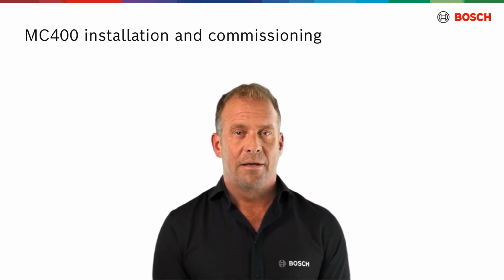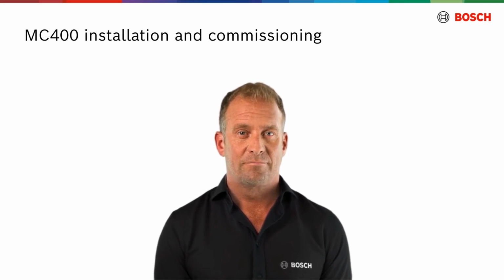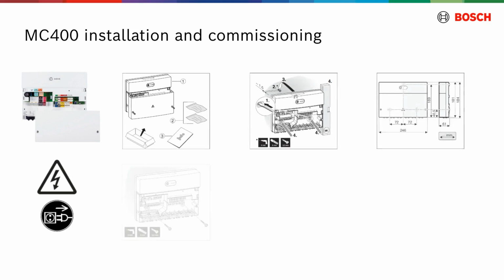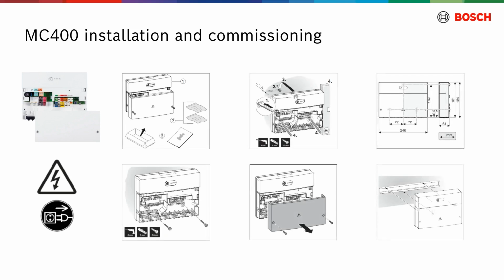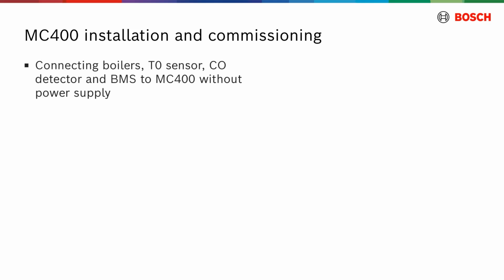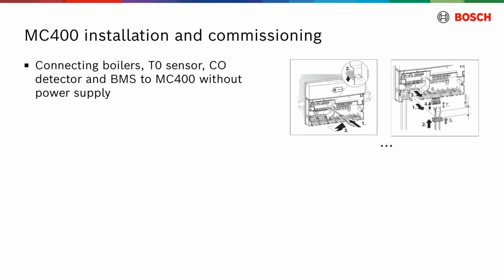The following sequence is essential for the installation and initial commissioning of the MC400 module. Before setting up the MC400, ensure that all heat sources and bus nodes are disconnected from power at every connection point. In accordance with the installation manual, install the module on a wall using a mounting rail or within an assembly. Then, connect the boilers, T0 sensor, CO detector set, and the BMS to the MC400 without a power supply.